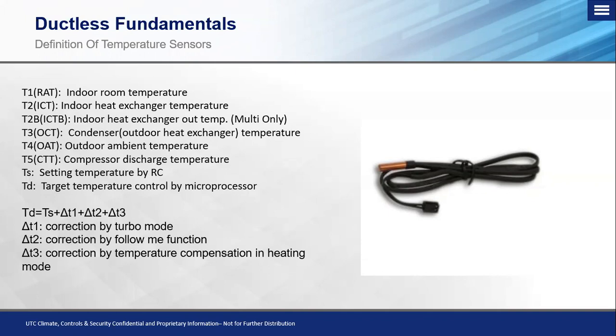Now we look at our Delta T2, which is a correction by follow me. This is an extremely popular option and one that I get questions on all the time. So on the wireless handheld remote controllers, they have a follow me button on there. And when you hit it, instead of taking temperature at our T1 sensor, so if we look back at that T1 up here, indoor room temperature sensor, that is the default sensing location for all ductless equipment. Okay, when we hit the follow me function, we are now saying, system, I'm not looking at T1 anymore. I'm looking at this remote controller. And it communicates to that particular indoor unit based off of an infrared signal.